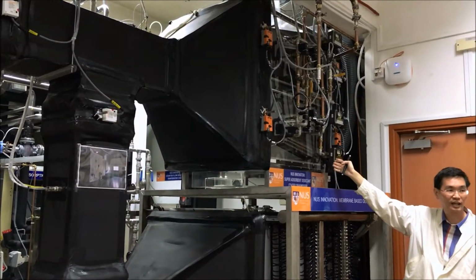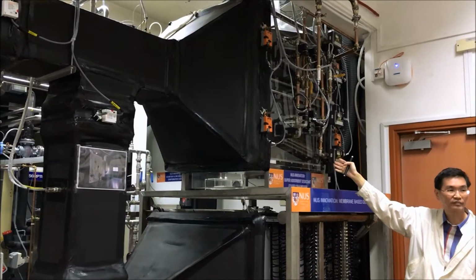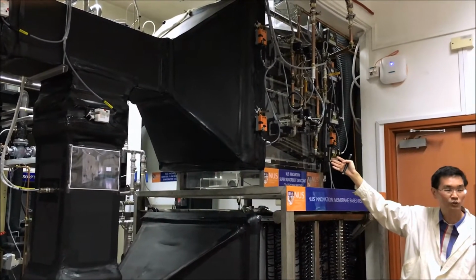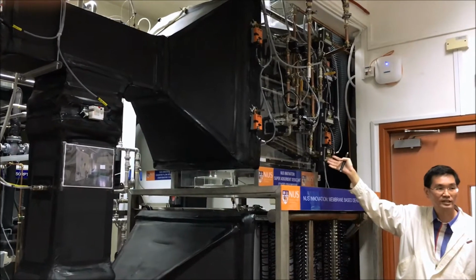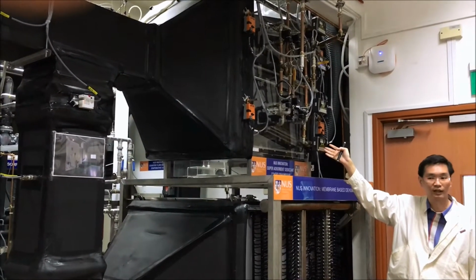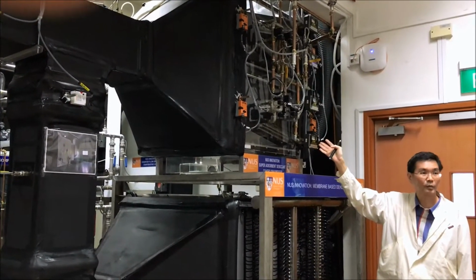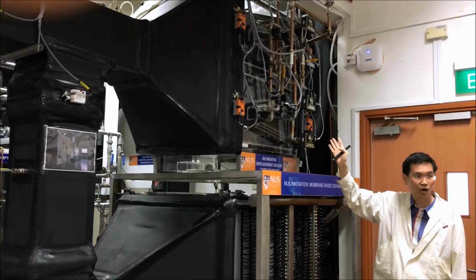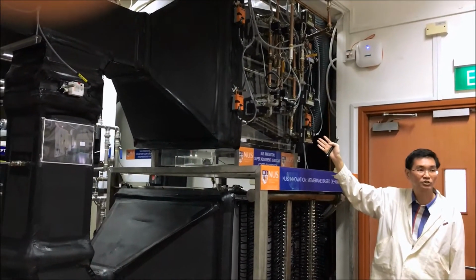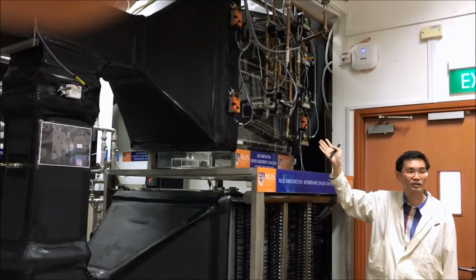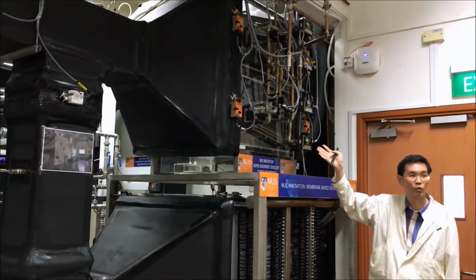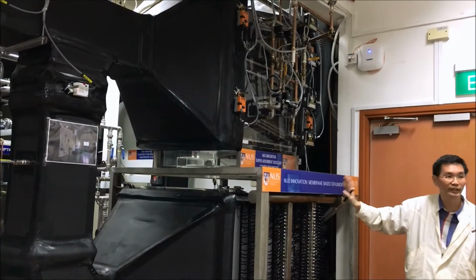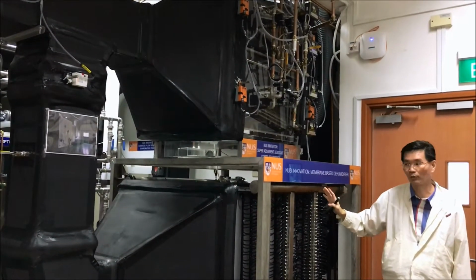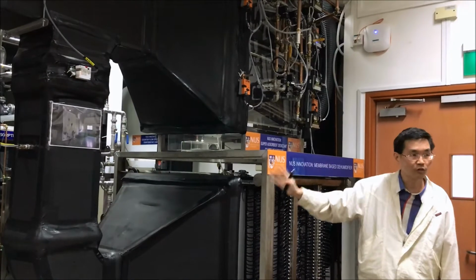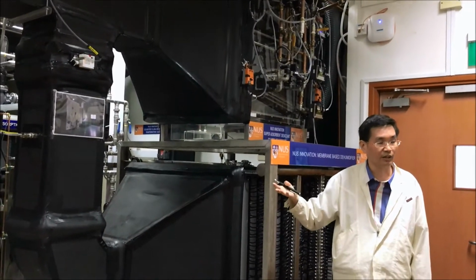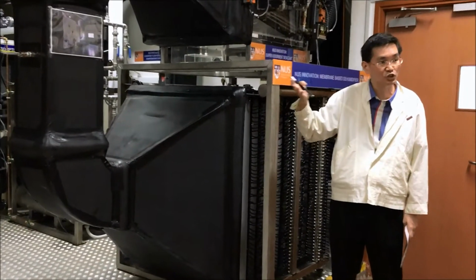better performing than the commercial silica gel, because it has 5 times more absorptive capacity, and also it requires less waste heat to regenerate, typically about 50 degrees of hot water to regenerate. In contrast, silica gel requires close to 100 degrees of hot water to regenerate. So these two systems will take care of the latent part, to remove the moisture from the air. Then our overall plant system can enjoy improved efficiency in terms of generating chilled water.